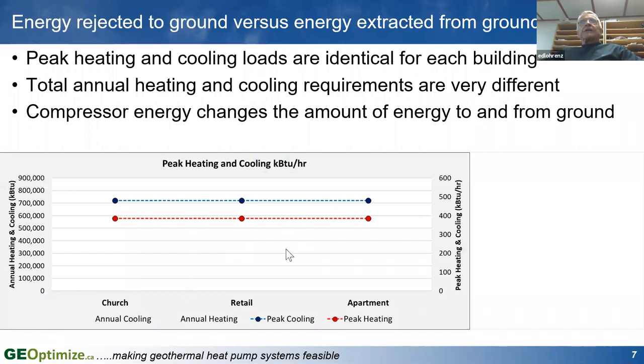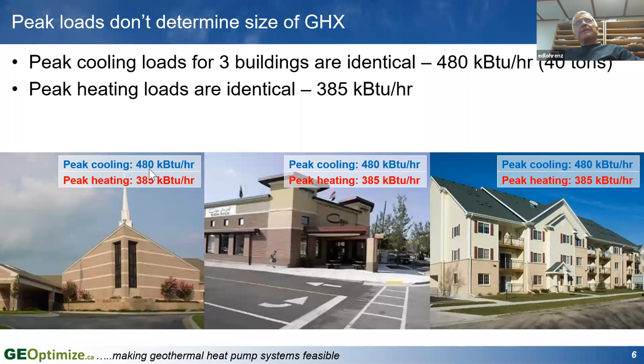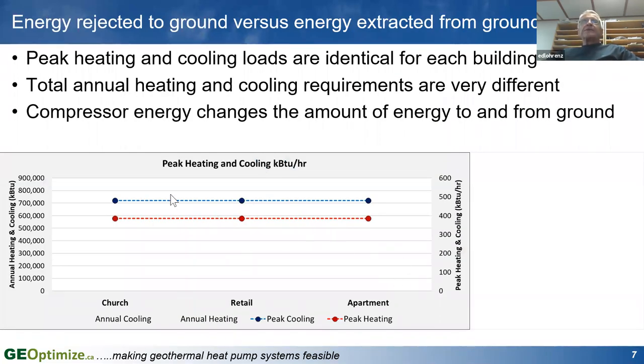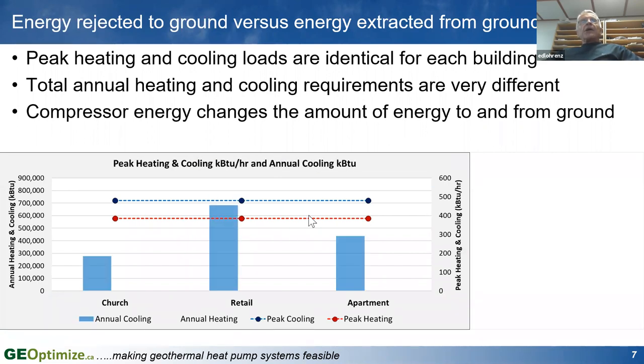And if we use the rules of thumb, that would suggest, because you've got 40 tons of equipment in there, that you would need about 8,000 feet of drilling based on the cooling capacity. The problem is that that doesn't take into account how many hours per day or per year that system requires cooling. A church, for example, only requires cooling for maybe 3 or 4 or 5 hours a week. A retail store, probably 70 or 80 hours a week, simply because of how many people are in the store, how many lights are on in the store. The glass in the store is a lot different than it would be in a church, for example. An apartment building is typically somewhere in between. So the amount of cooling that you're doing on an annual basis is a lot lower in a church than it is in a retail store, and the apartment building is somewhere in between.